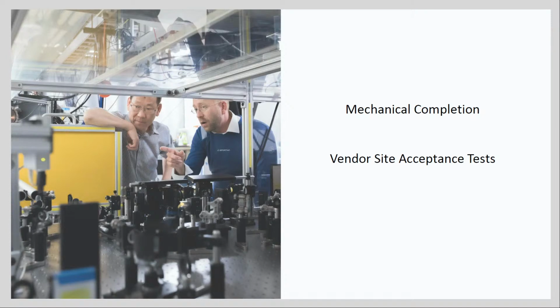During the SAT, the vendor can confirm that they have in fact delivered contract compliant equipment and that it meets all technical requirements and is therefore available to proceed with further commissioning. So the vendor will sign off on their equipment saying, yes, it does meet technical requirements. The vendor, the contractor, the owner, commissioning team, whoever's involved there will sign off and say, okay, this piece of equipment's good to go. Now it can be used for further testing in the rest of the subsystems and systems.